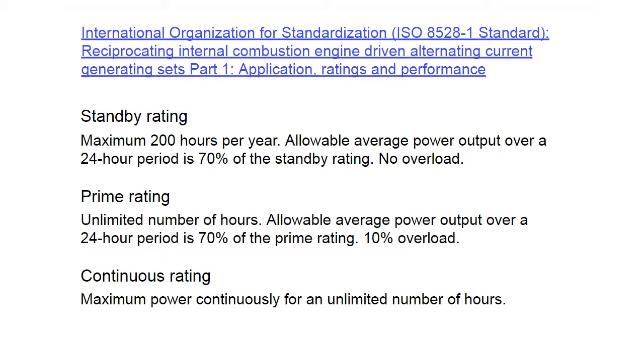The prime rating is unlimited hours. Again, it has a 24-hour period at 70%, but it does have overload. So a lot of times, instead of a standby rating, you'll see a prime rating being used for data centers just because of that reason, because you're going to have a constant load over a long period of time. The other rating is continuous. This is maximum power continuously, unlimited number of days. This might be a mining operation or something like that where you're going to be running without utility.